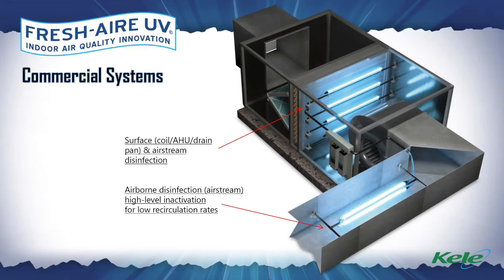So of course, the first picture you see there is UV lights on the air handling unit, on the coil, always addressing the coil, the surfaces, and continually treating the air as the air recirculates and passes through the coil section. But then we have this other product, which is a parallel orientation to airflow, which is mounted in the ductwork. And this is designed to maximize the exposure time between the UV light and the moving air. So typically you will get a much higher first pass reduction when mounting a system in that configuration versus mounting a unit inside the air handling unit. But the question remains, what is the right product for you?